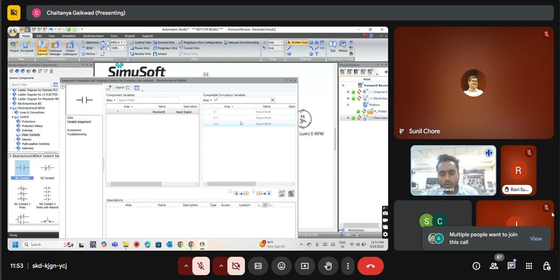So how easily we can show the interlocking - now it will get held, right? But when my circuit is in forward direction, my reverse direction button should not work, or the coil should not get energized. So I have to give the interlock, so I have to connect an NC contact between them.